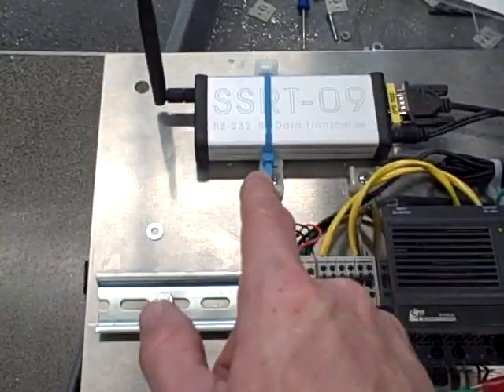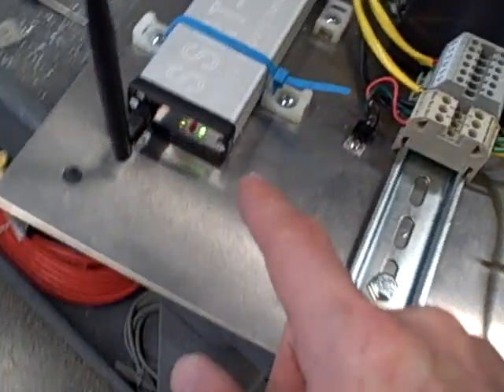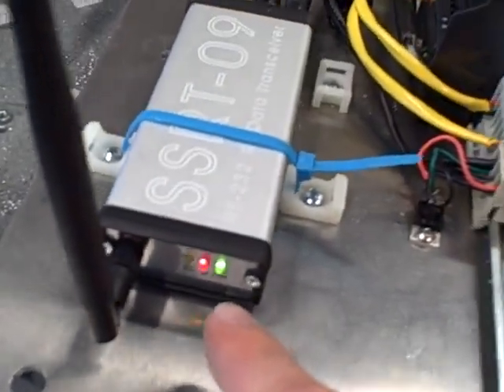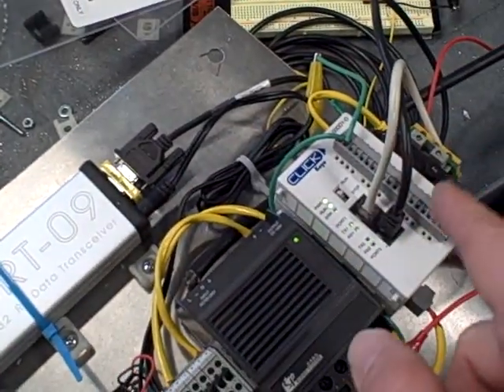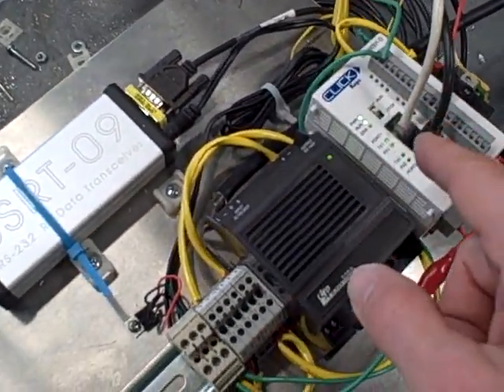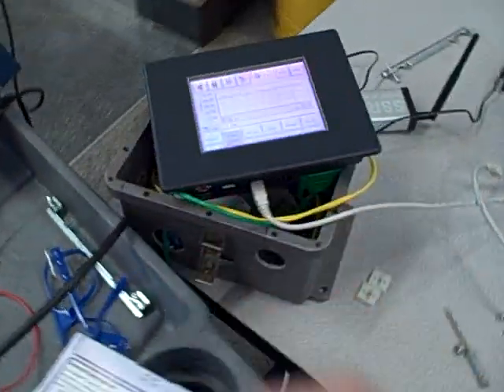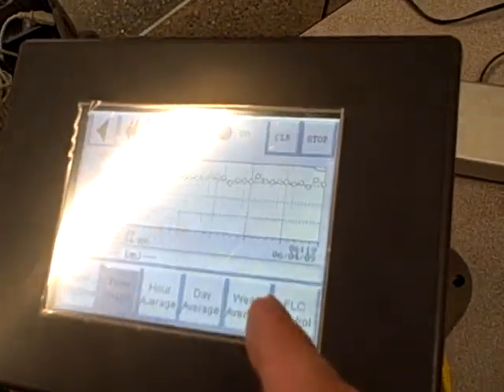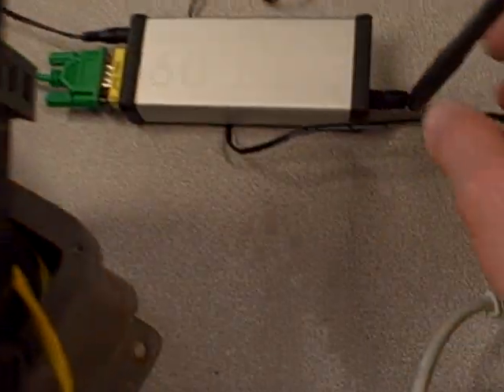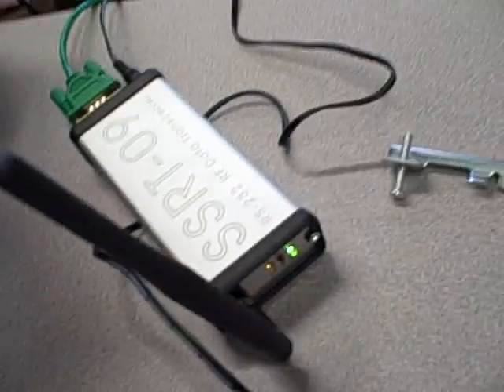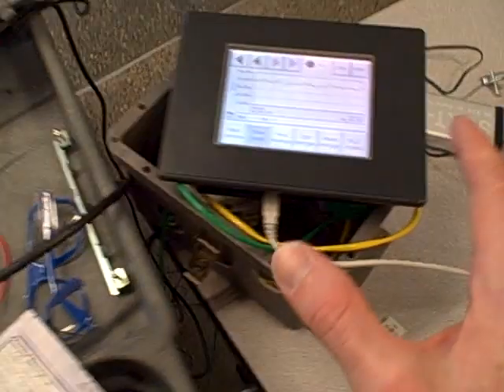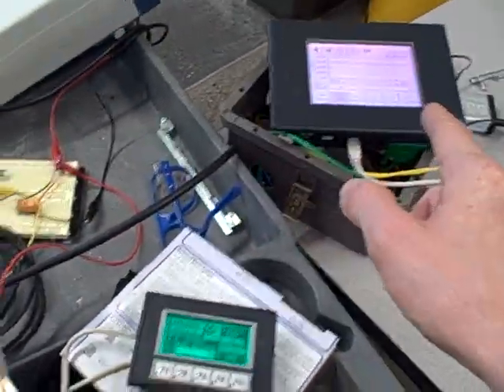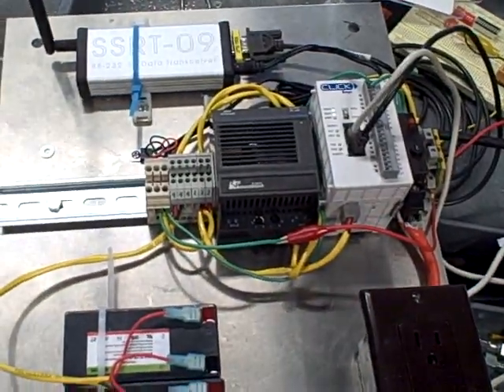Here we have our spread spectrum transceiver at the PLC end. You can see it transmitting and receiving. It's communicating 9600 baud using Modbus protocol, essentially acting as an interface between the PLC and the HMI touchscreen. On the HMI side, which will be in the maintenance shop, we have a matching spread spectrum serial unit. You can see the transmit and receive lights blinking there. So essentially, the two radios take the place of a long cable that would normally connect the HMI to the PLC.